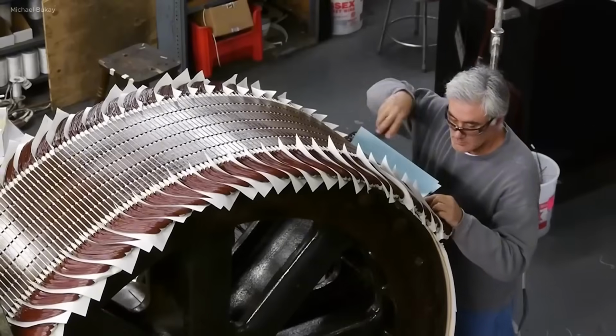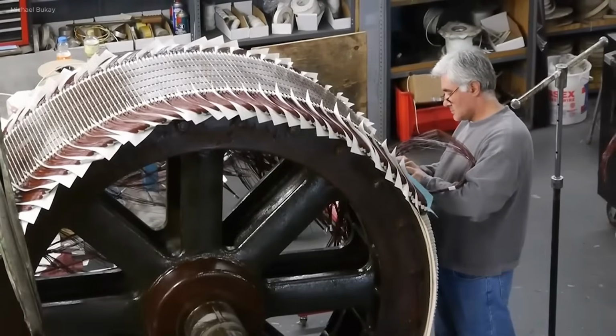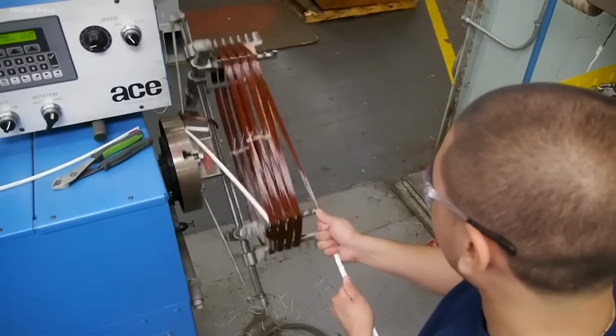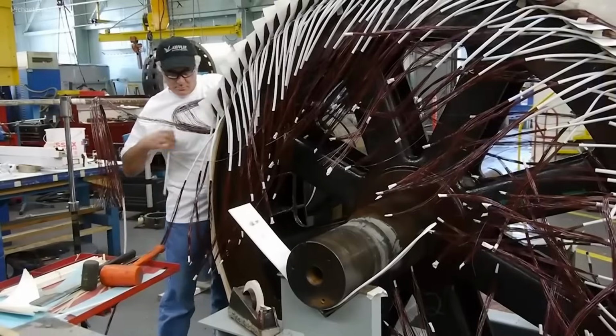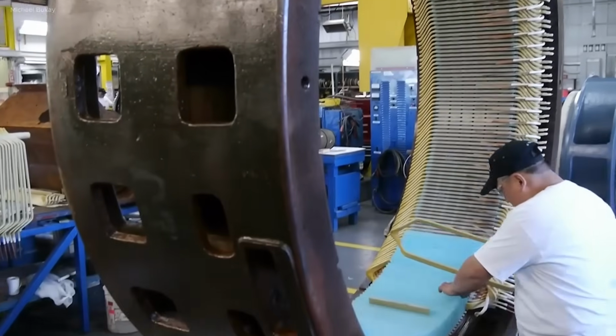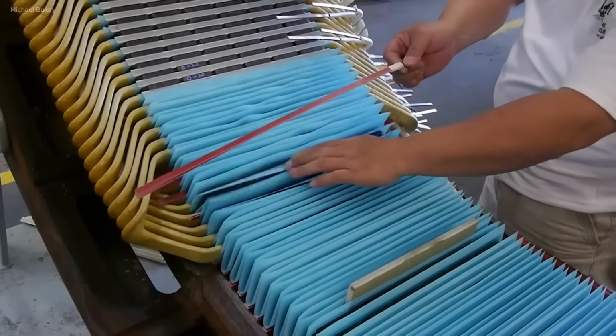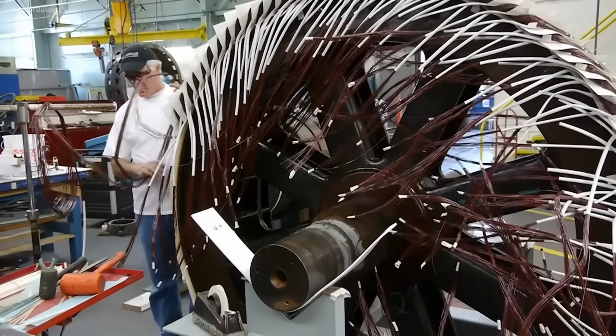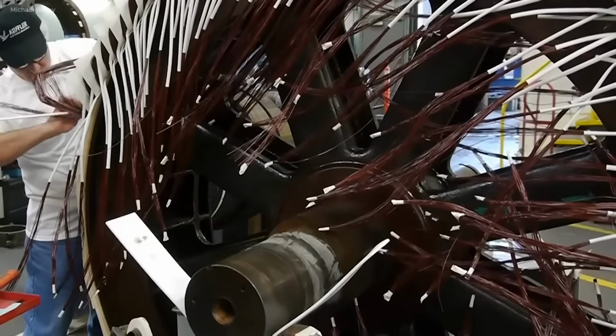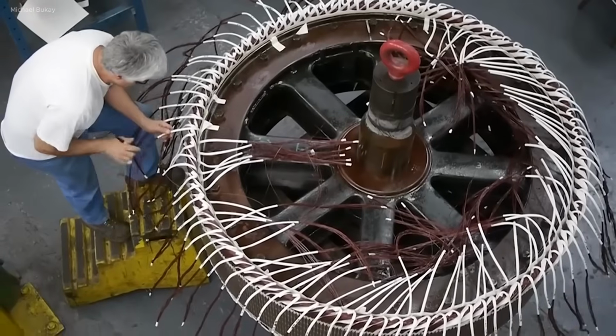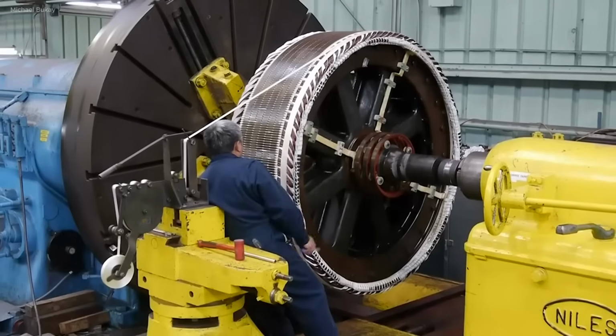The rewinding process of a large motor at Koffler begins with disassembling and inspecting the motor to identify faults. The old windings are carefully removed from the stator, and the core is cleaned thoroughly. New coils are then precisely wound and inserted into the stator slots following exact specifications. These coils are connected, insulated, and securely tied in place.